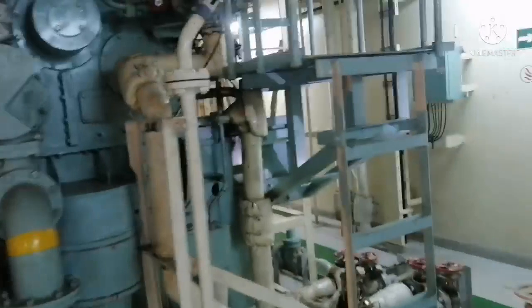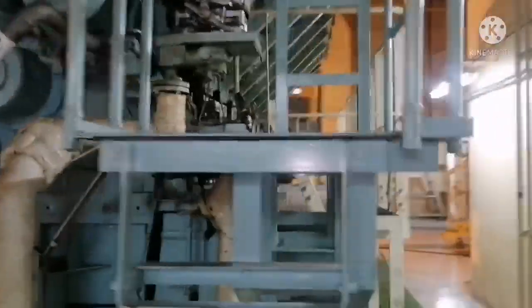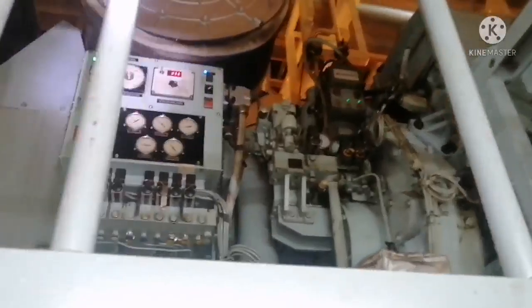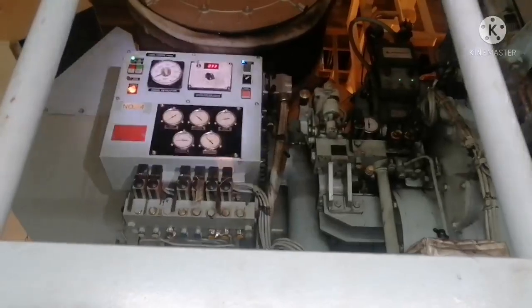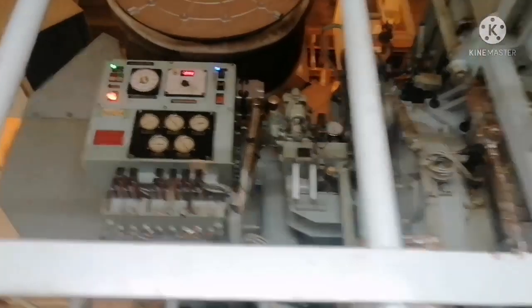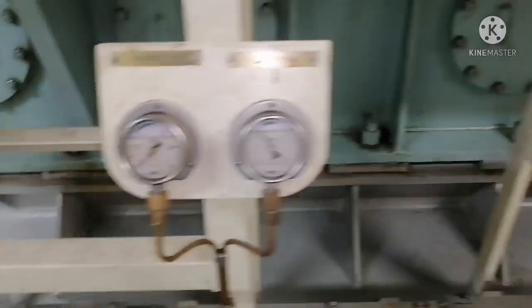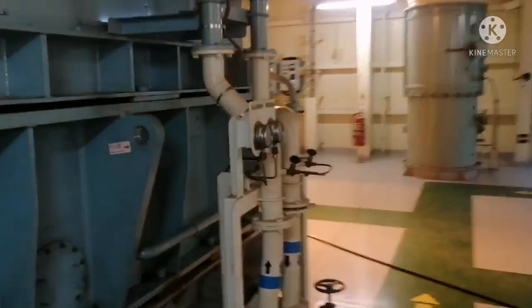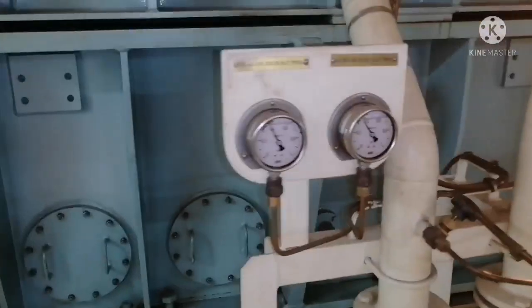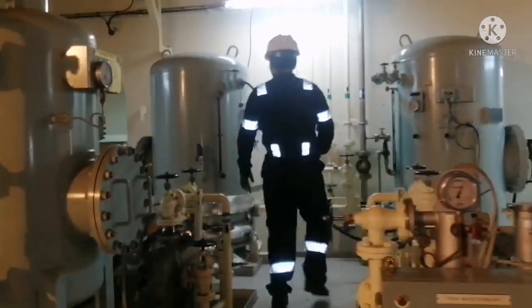And the generator which is not running, you have to check whether the lube oil priming pump is running and the engine ready to start light is glowing. And also you have to check the lube oil sump level, and you have to check the cooling water pressure, inlet, outlet and everything. And what else? Have a visual round.